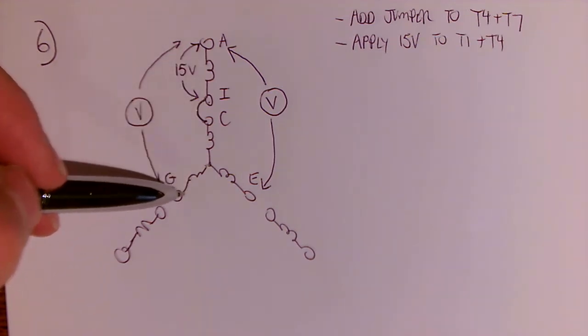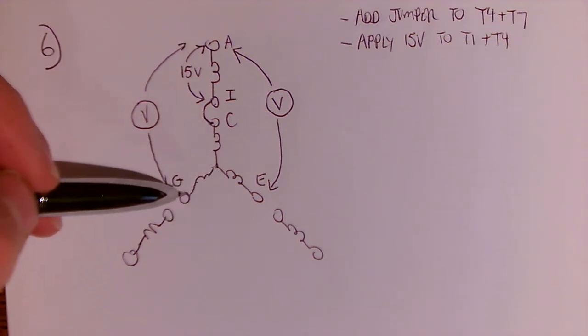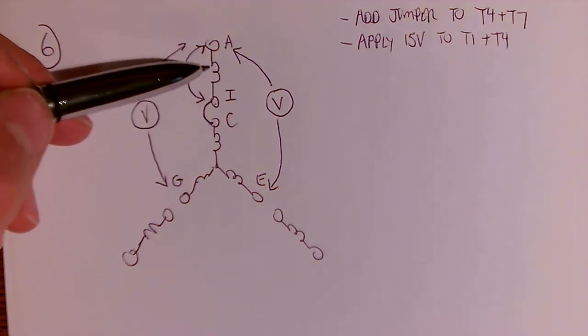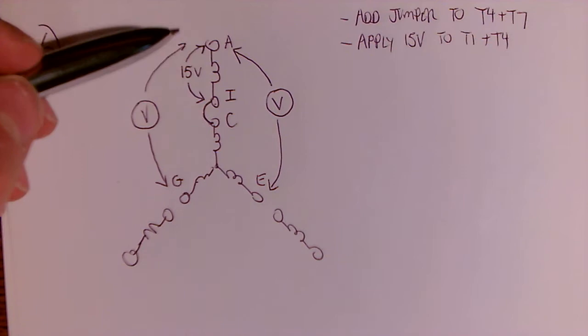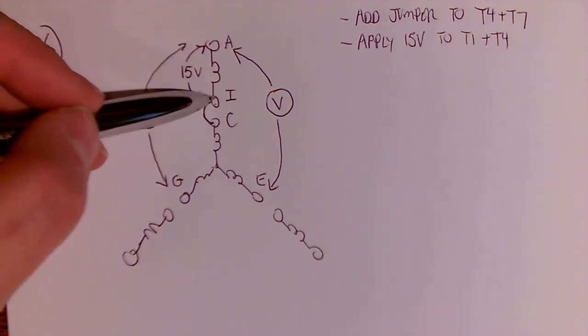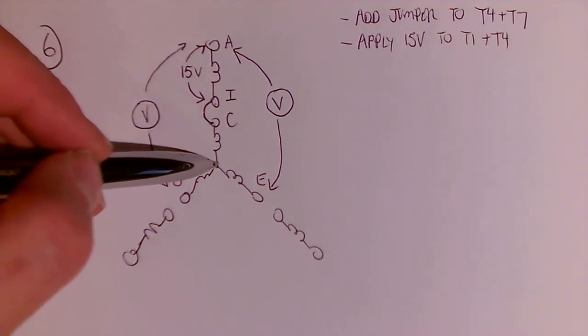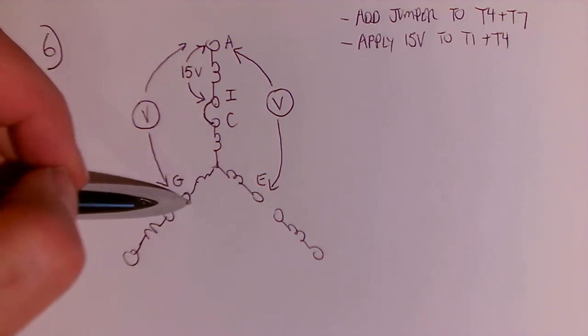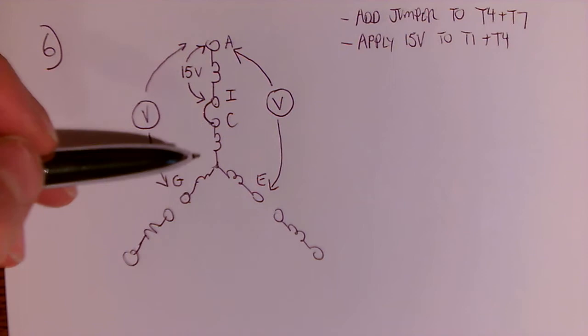And I'm also going to induce almost 15 volts in these other ones, but again, it's going to be a little bit less. Now what's going to happen is if the polarity is correct, so if this is negative and this is positive and this is negative and then this would be positive, we can't get in here and actually measure here, so that's why we have to measure these T8 and T9 terminals in this case.